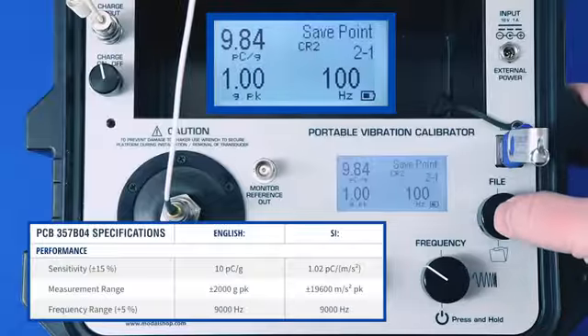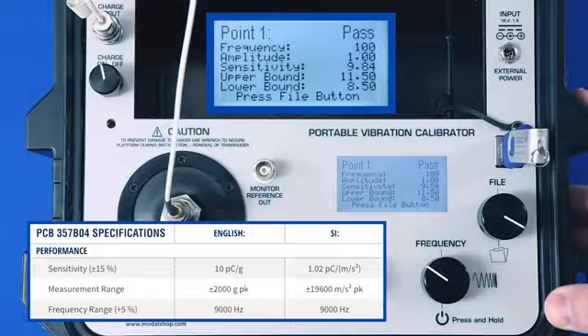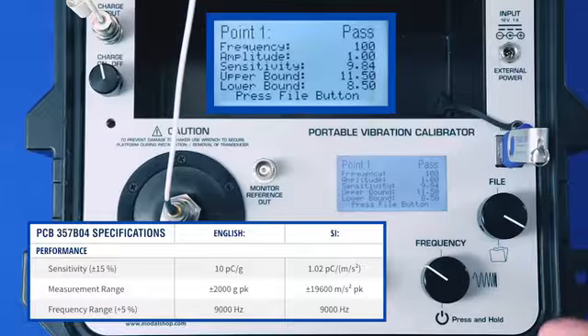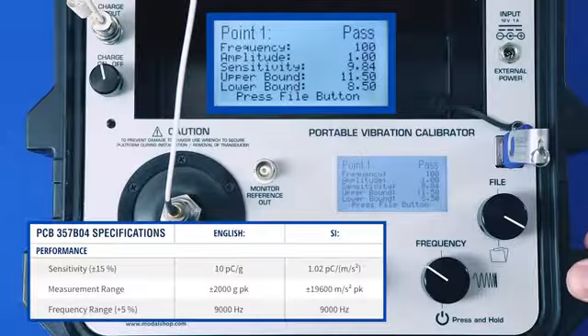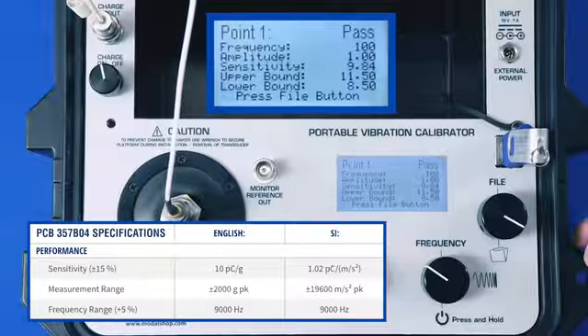I can save that test point by pressing the File button. You can see that the sensitivity was 9.84 and the tolerance is plus or minus 15% at 100 Hertz. So anything from 8.5 to 11.5 picocoulombs per G passes calibration. And you see that data on the screen.